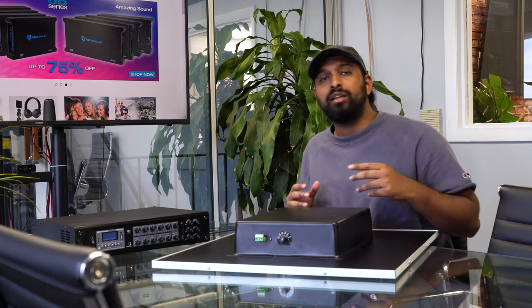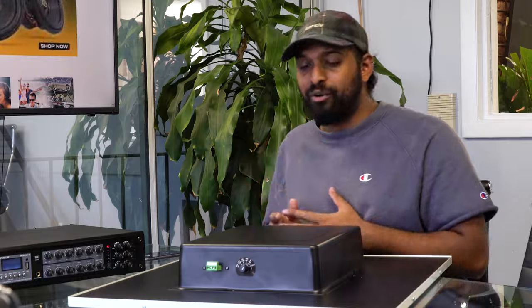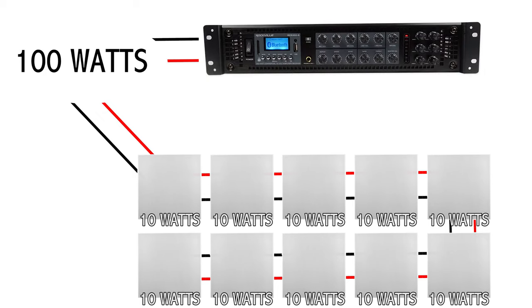The one thing you do want to double check in a 70-volt system is the amount of speakers you have and what wattage amounts they're all tapped at and make sure that your amplifier can easily produce that power. For example, if I have 10 of these speakers and I tap them at 10 watts, I want to make sure I match it with an amplifier that can easily produce 100 watts. Another unique thing about these speakers is they were built with a frequency response that's really great for announcements and chimes.